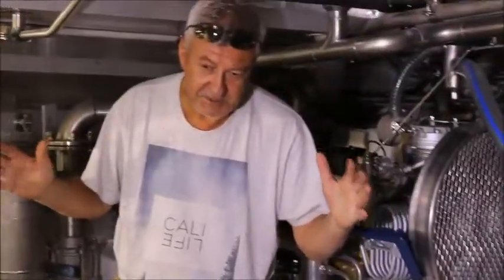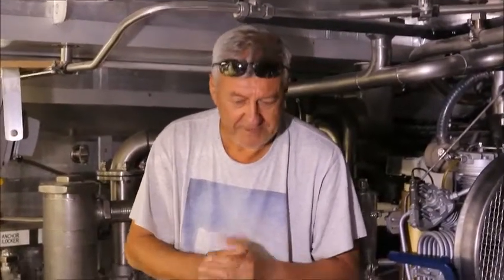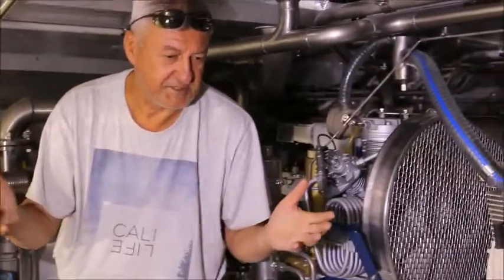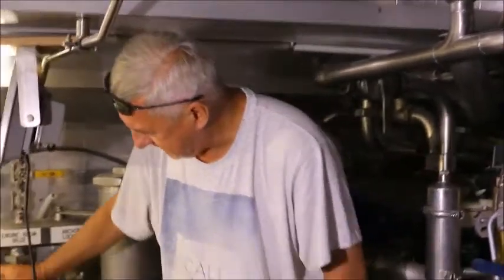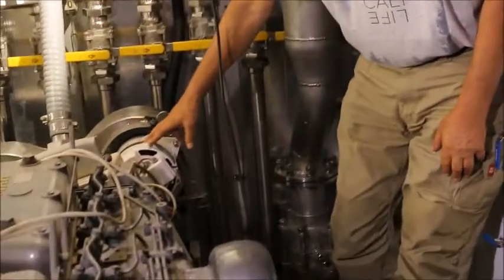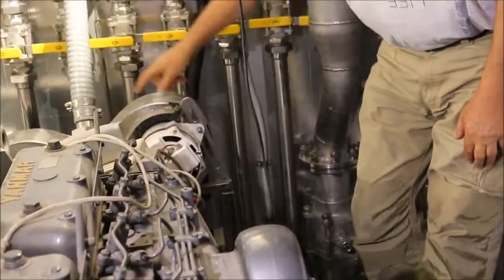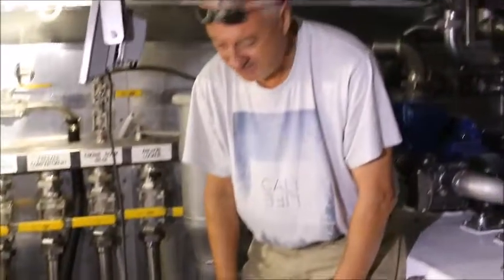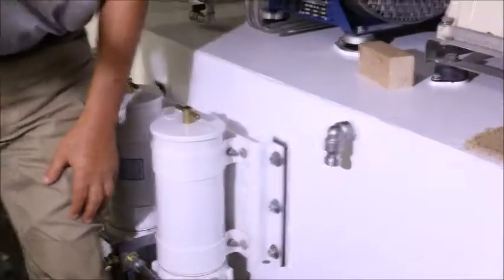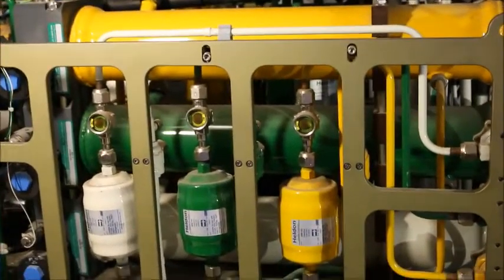We had one big three-phase generator and one big single-phase generator, and there was no way to fit it anywhere here. So Theo came to me and said, what do I do with this? I said we'll have to go DC hydraulics and a small AC single phase. So basically we design a DC generator here, 24 volts, 200 amps. Then we have compressors running off the engine, and we have a combi system here that does all the air conditioning, refrigeration, desalination and deck wash, all in one, in that box.